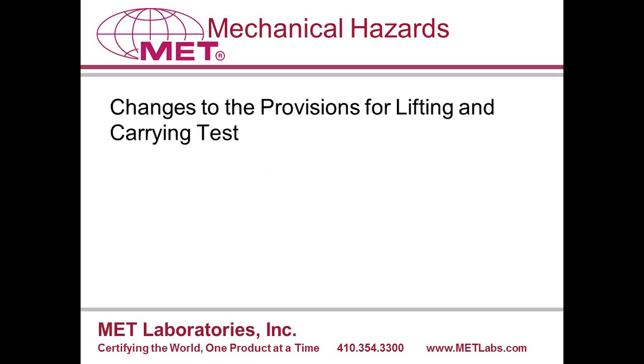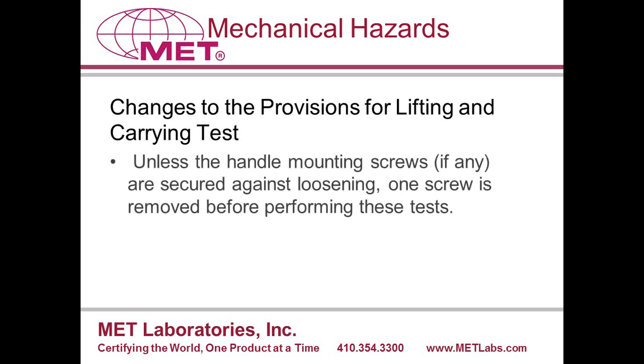There's been a small modification to how the handle test is performed, and that is, if it is possible for a screw holding a handle to become loose, then the test is performed with that screw removed. The criteria is the same. There can be no failure or deformation of the handle.